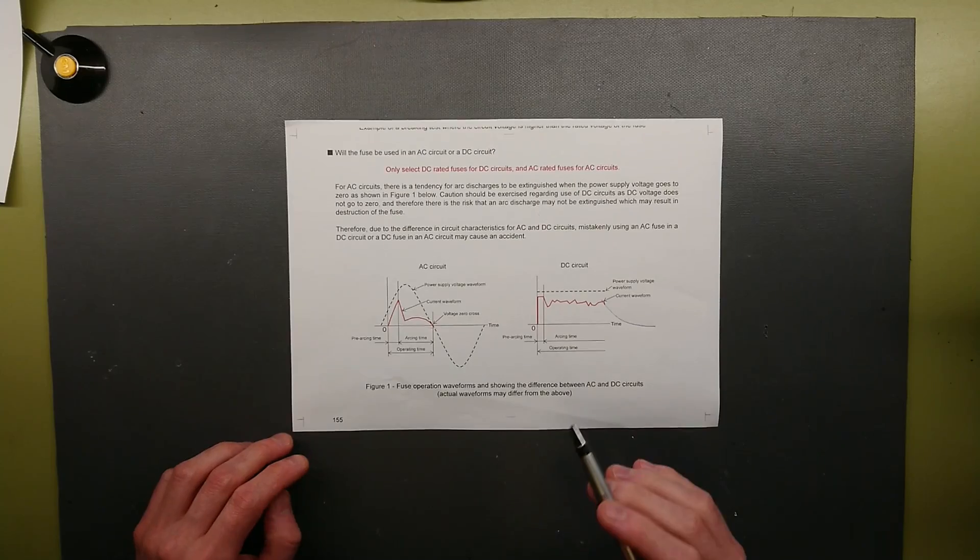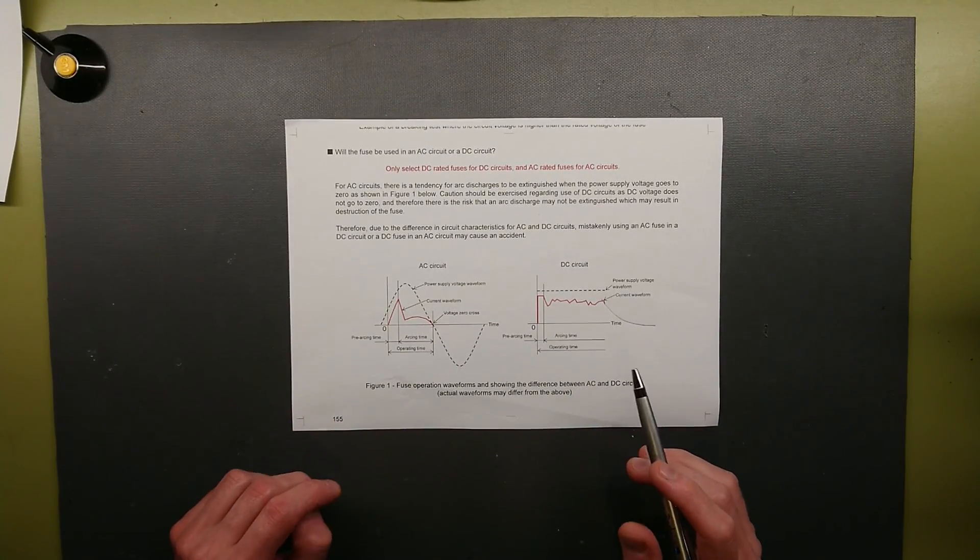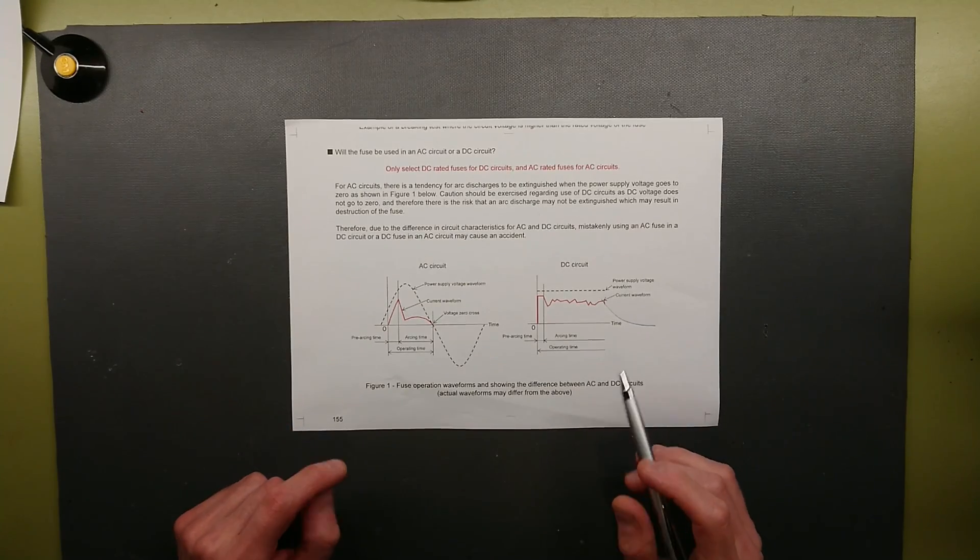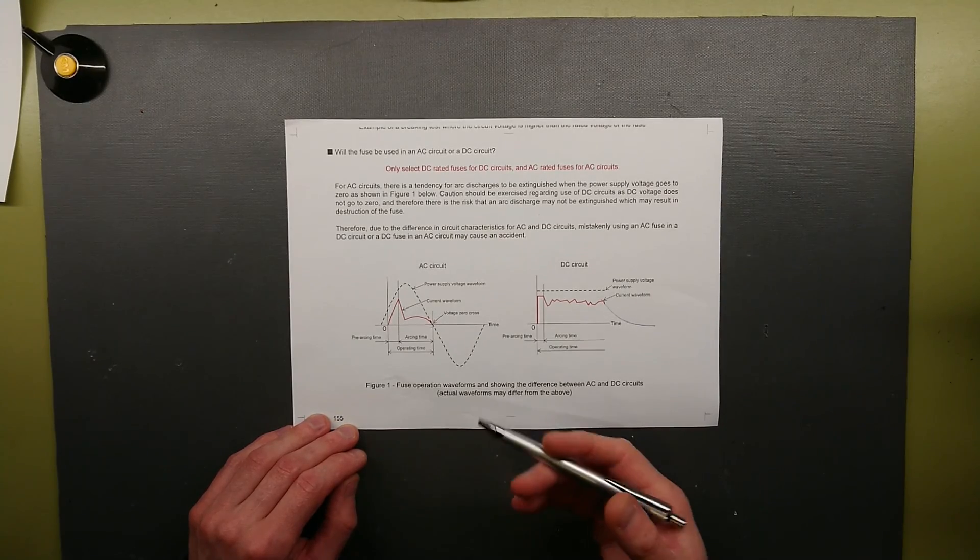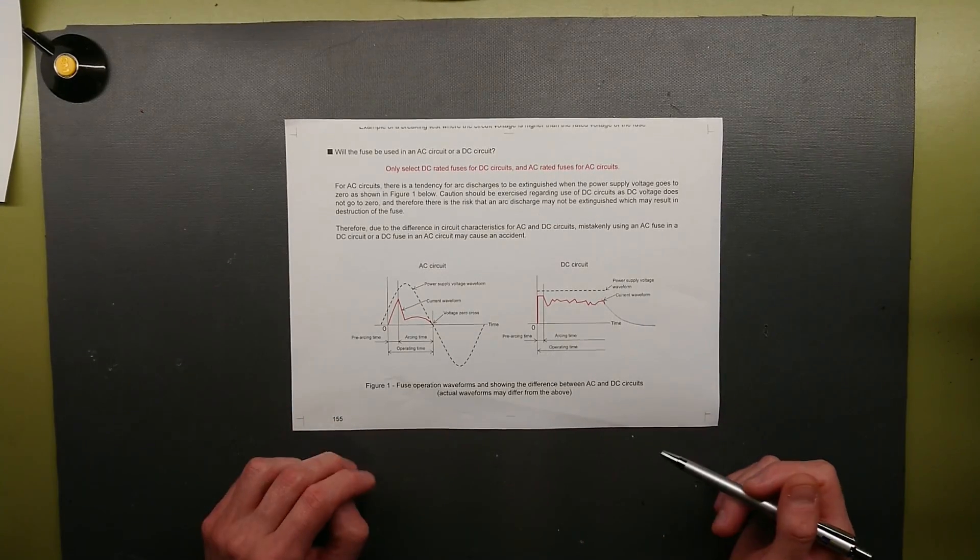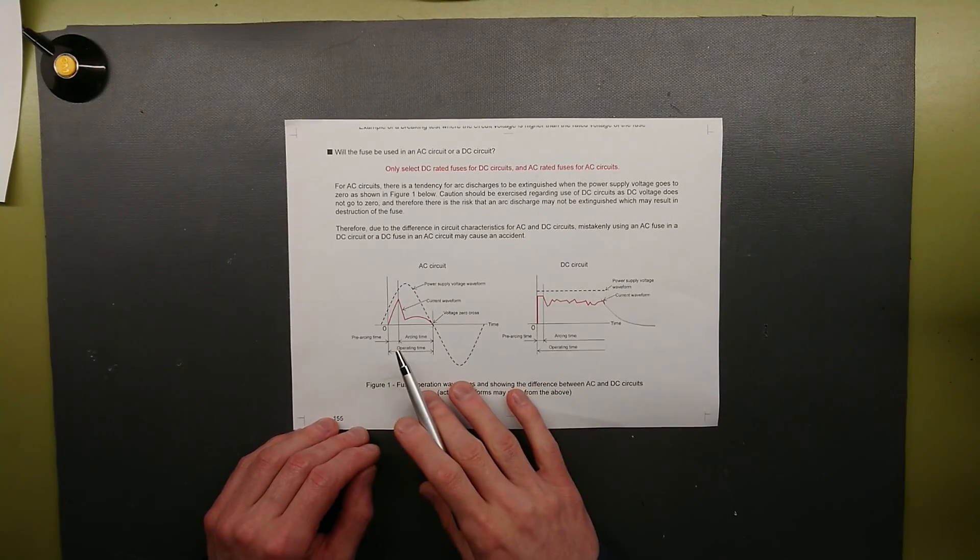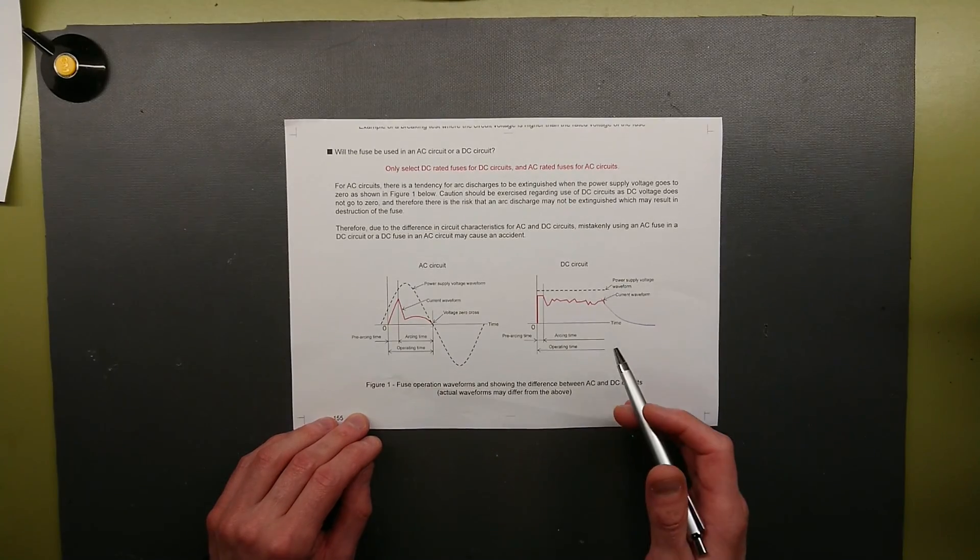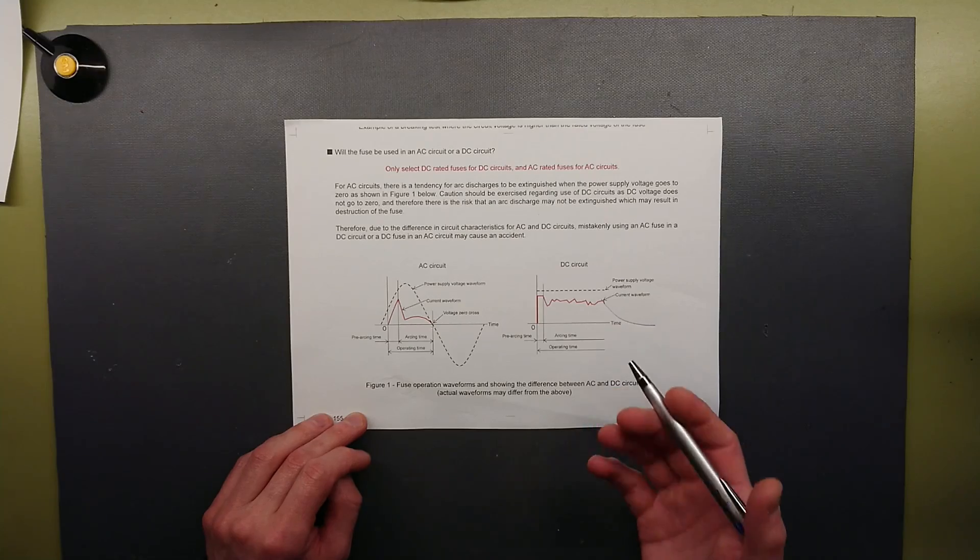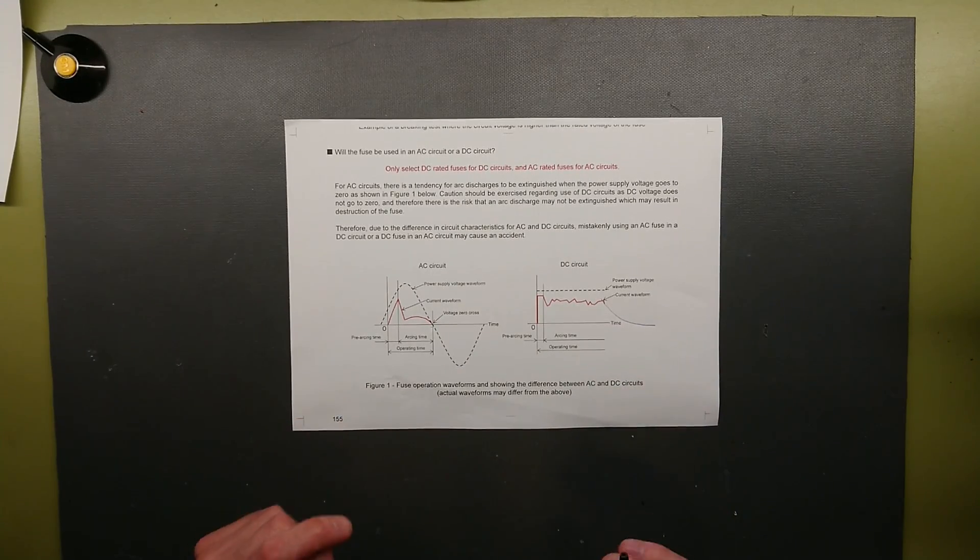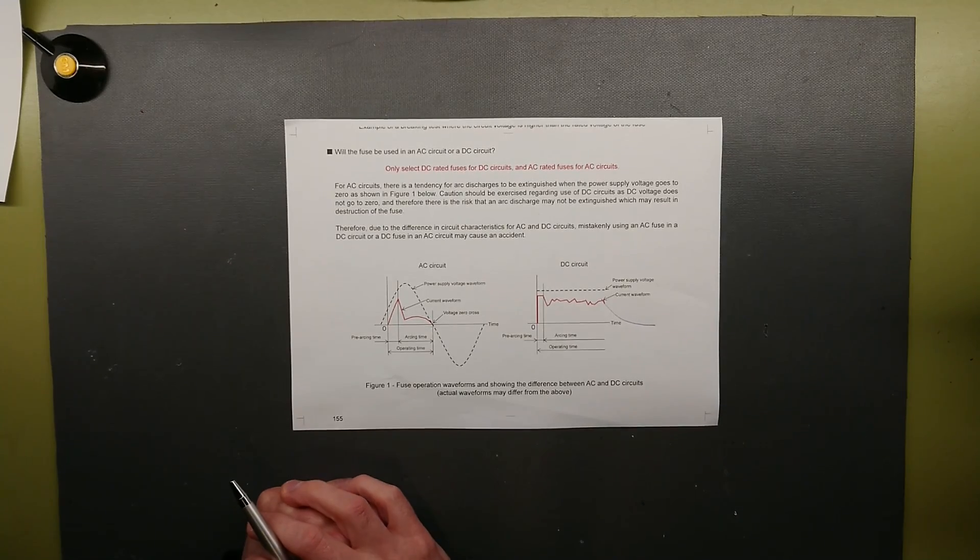Some AC fuses can be used for DC. You will find a very extreme derating on them. What is an AC fuse meant for maybe 500V AC can maybe only be used for 100V DC. That is because the I2T ratings for AC fuses is much lower than DC fuses. But you will most likely never find a DC fuse that can be used for AC. Always choose your fuse according to your application and circuit.